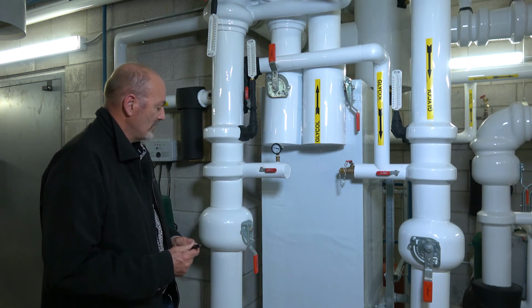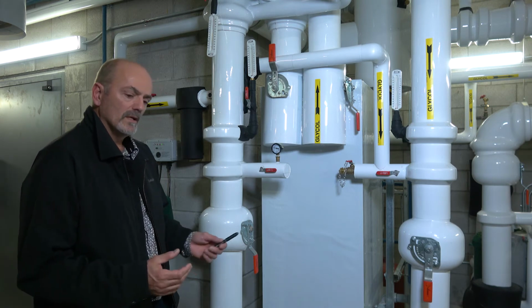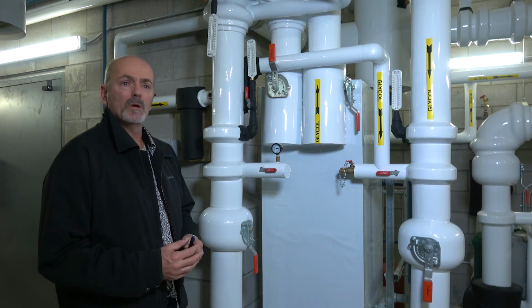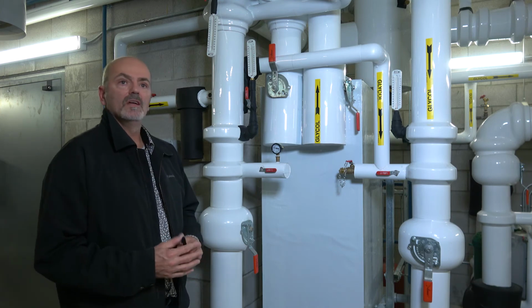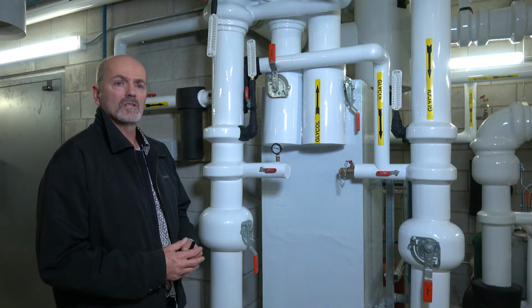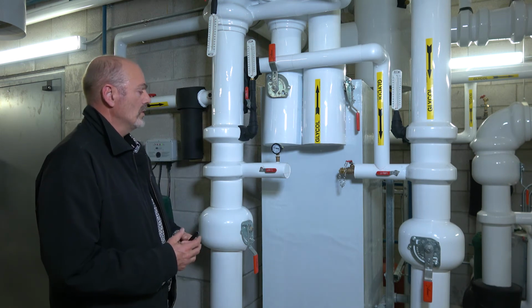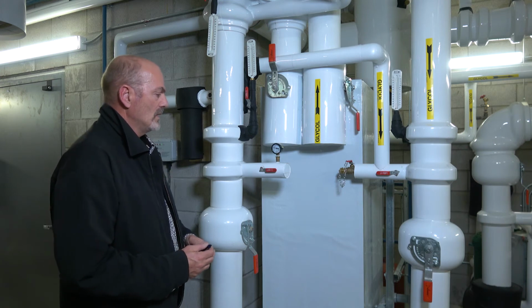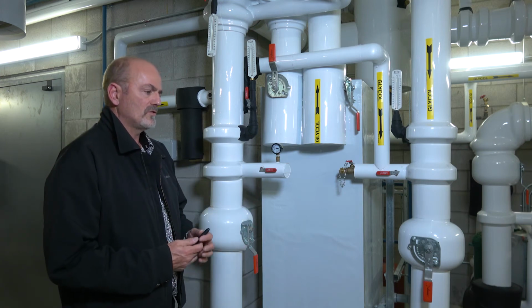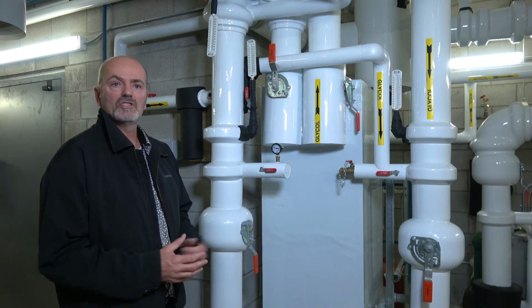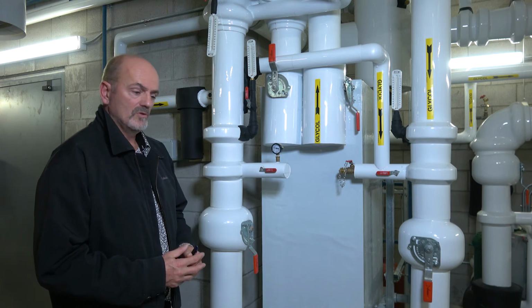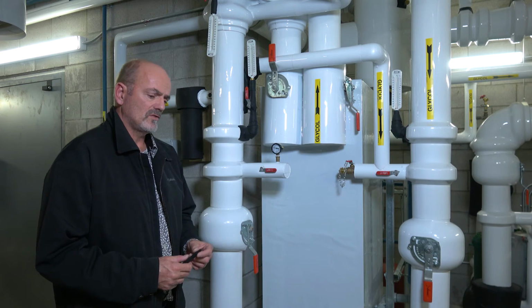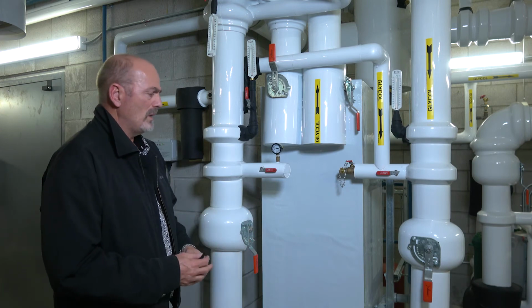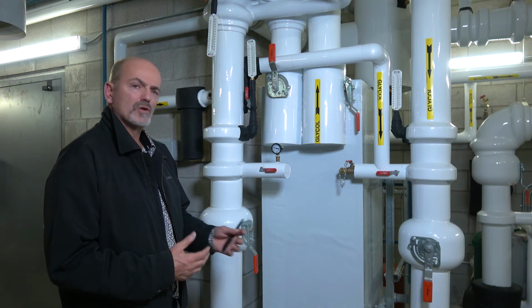It's an ASME pressure vessel, and essentially the only thing that can cause an issue is you could get a leak down the road between a plate and a gasket. If that's the case, the insulation would have to be removed, and a service contractor that's familiar with the product and has the tools would open it up and replace the gasket. Down the road, in like years down the road, there is a possibility to need to open the entire heat exchanger up and clean every plate and replace the gasket set, which is called a complete refit. That can happen as the system gets older, there's more debris, it has to do with maintenance, you're getting dirt in there, entrainment of untreated fluid precipitates out on the plates, so its capacity drops. And that's about it. There's not much to it, no moving parts.